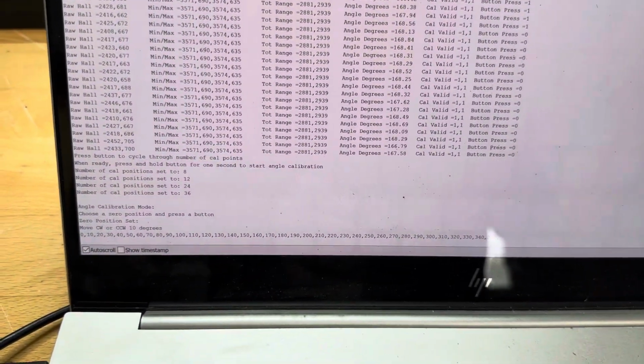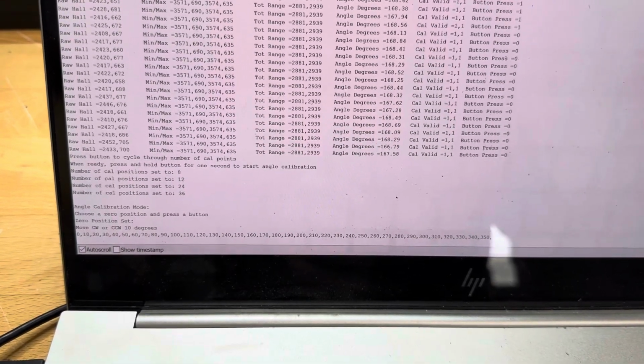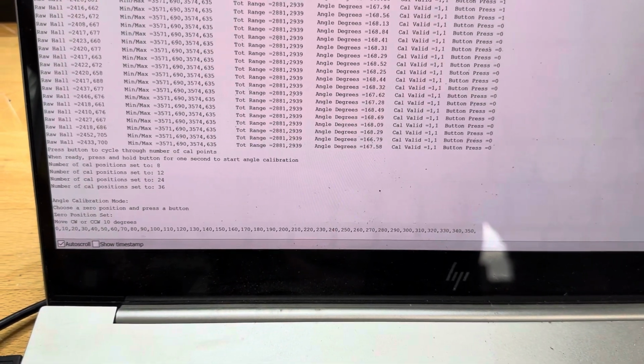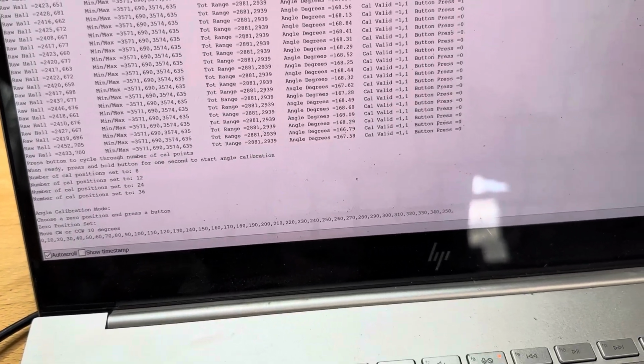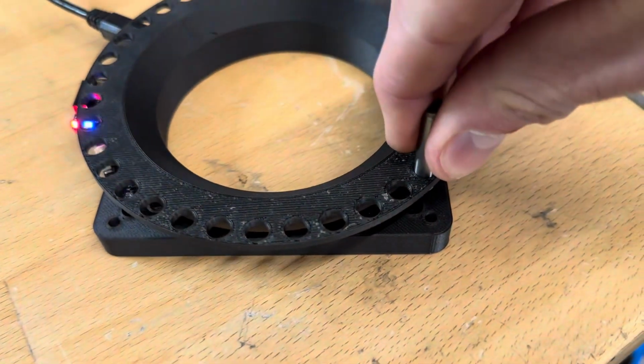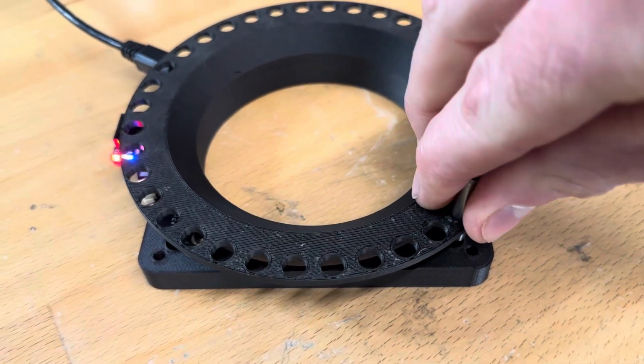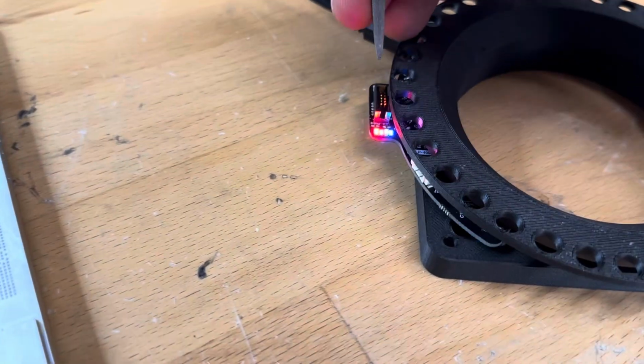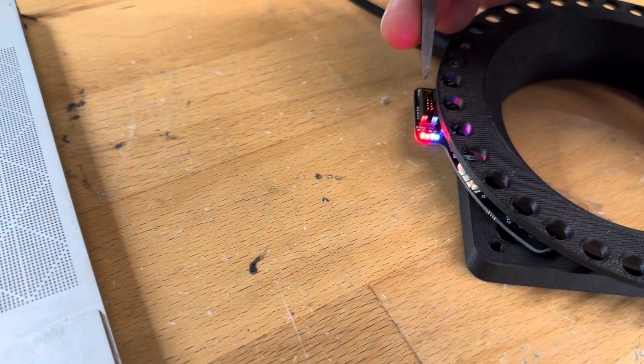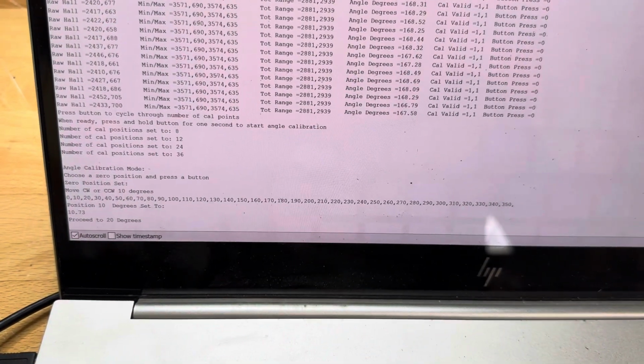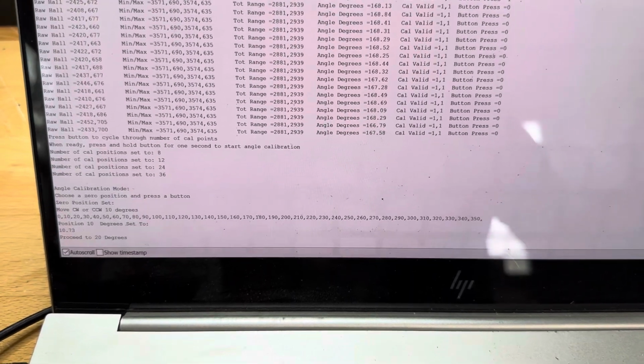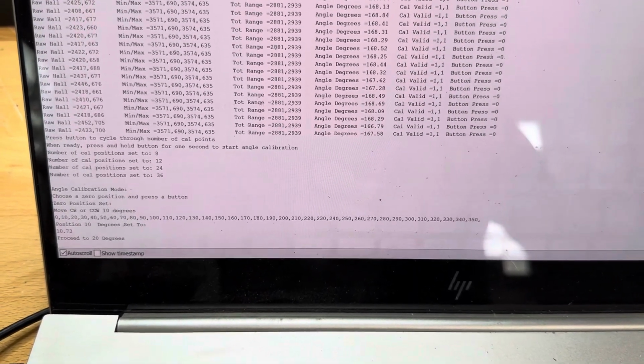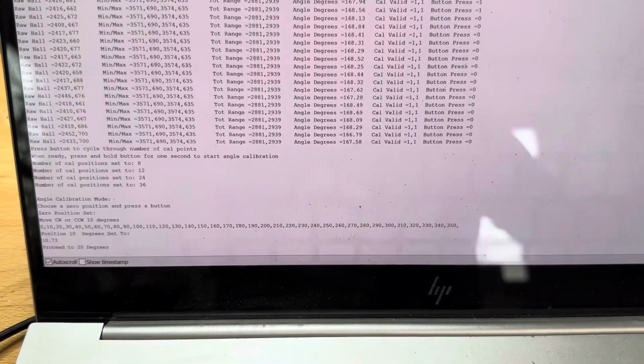Now after I've done that, it's moved on and said, okay, now you're gonna move it through all these different rotations and record the settings. So it wants me to go 10 degrees. So the first thing I would do over here on this rig, I would move my pin to the 10 degree mark, go into my alignment tool, hit the button, and if I press the button correctly, now the computer will tell me, okay, so I moved the rig physically 10 degrees and the sensor reported 10.73 degrees. So you can already see the first point in our calibration, we'd be linearizing between 0 to 10, in actuality between 0 and 10.73.